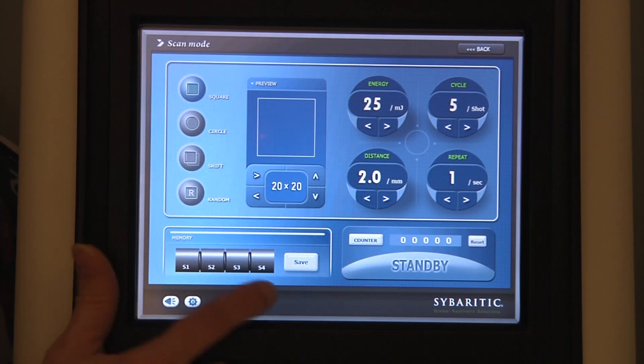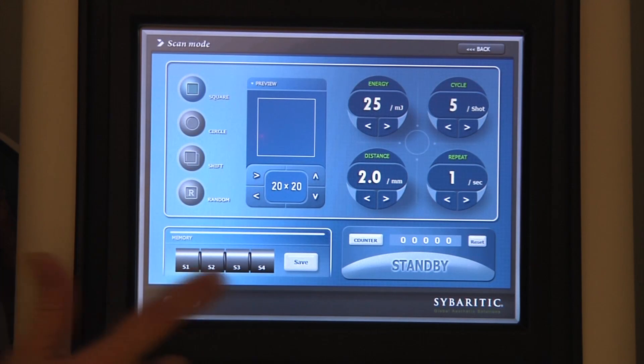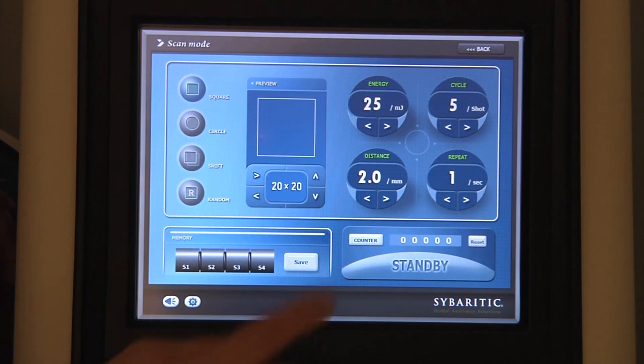We also have the ability to save commonly used parameters. So if one has a particular indication they do more commonly, they can program that in for ease of use. There's also a shot counter that you can use to keep track of how much energy is delivered to the patient.